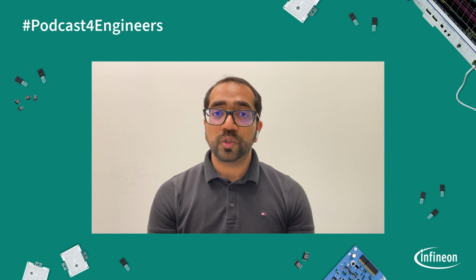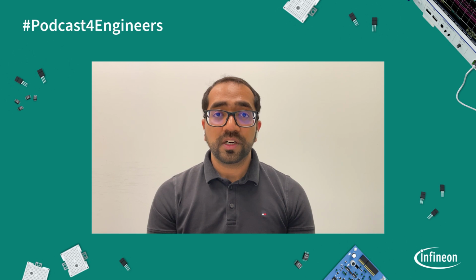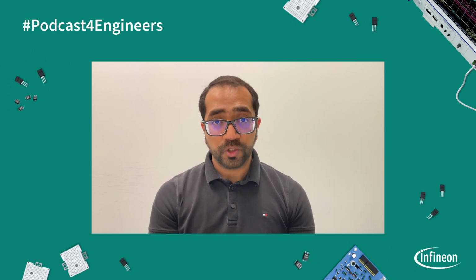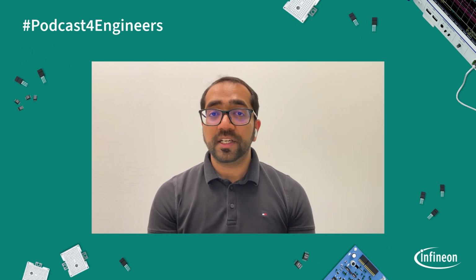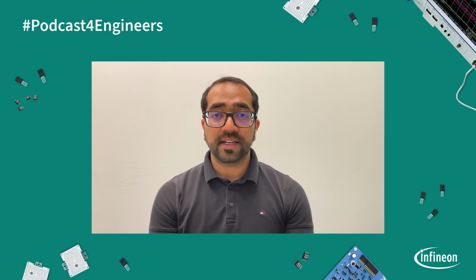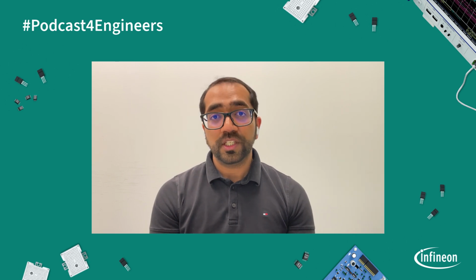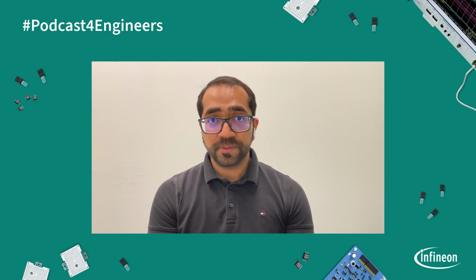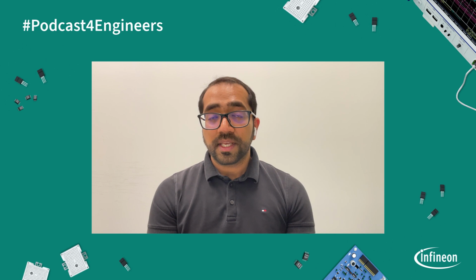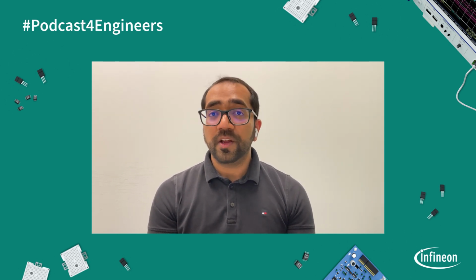So we use a hot swap controller. A hot swap controller basically works with an external MOSFET. The controller controls the gate voltage of the MOSFET and operates the MOSFET in a linear region. At startup, the MOSFET acts as an impedance between the capacitor and the backplane and slowly charges this output capacitor. And once this capacitor is charged, the FET goes into a fully on state, providing very low impedance.